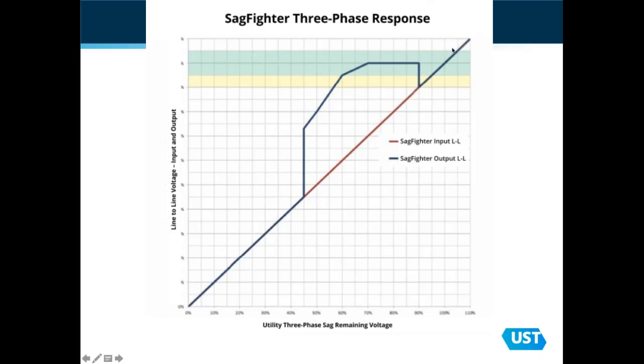So we've got incoming voltage coming in, and when that voltage hits the 90% threshold that I mentioned, the Sag Fighter comes on, and it tries to get the voltage back to nominal within plus or minus 5%, which is represented by the green. And down below here is the voltage sag. As the sag increases in voltage, the Sag Fighter continues to correct all the way down to 60%, which is our specification. At 60% of nominal voltage, we're still maintaining 5%. And then if the voltage goes down below that, you can see it start to fade off.